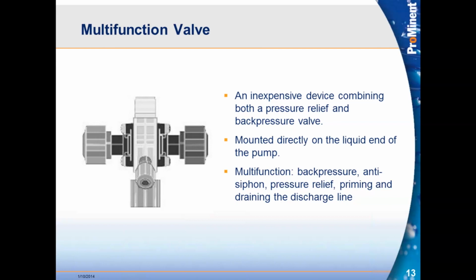One of the other things that the multifunction valve can do for us, we can manually open that pump to atmosphere or back to the supply tank, and that's going to help us with priming. So another function of that is kind of helping us with priming without really coming in contact with that chemical that could potentially be a pretty nasty chemical for us.